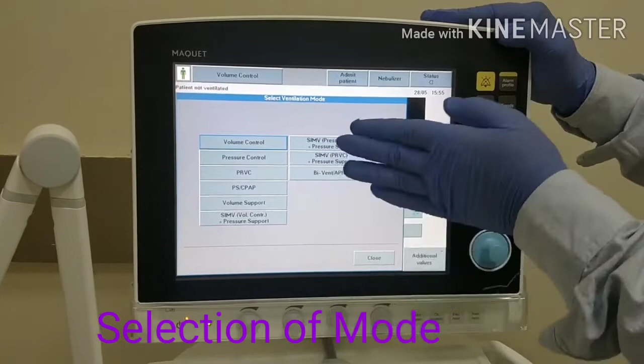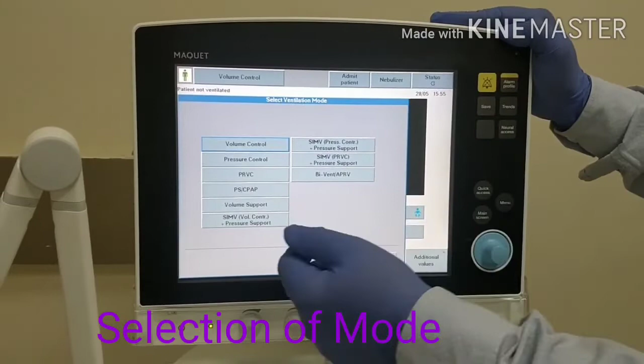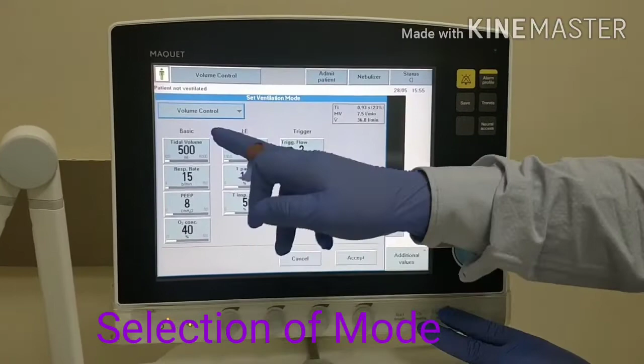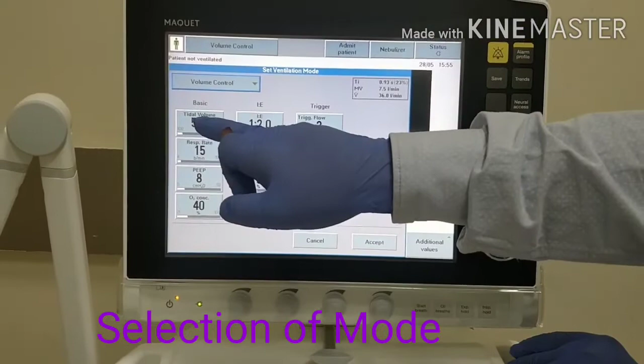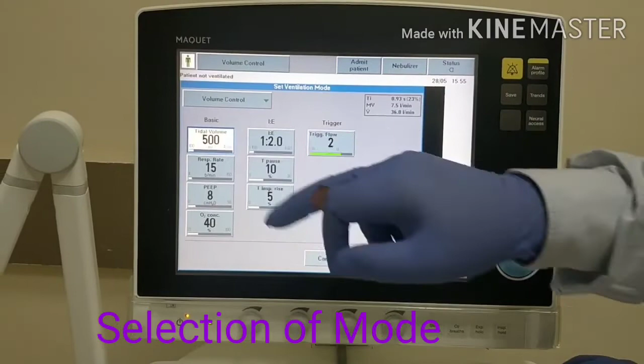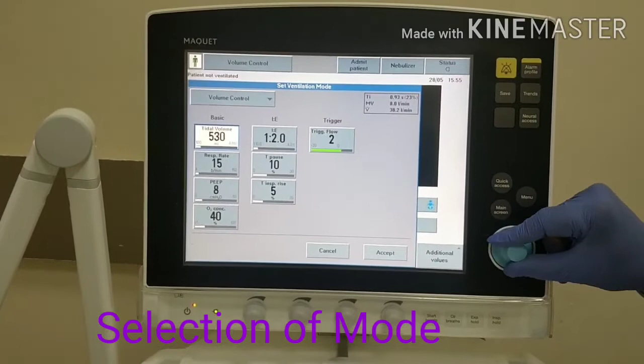Here we will see all the modes available in this ventilator: volume control, pressure control, PRVC, PS, CPAP, like this. So we can select any one mode from these. I will select volume control. Now different parameters of volume control are showing. First, how to change the parameter. First I will select tidal volume. It is now 500. By using this rotary knob, we can change the value of the parameters and just press it.